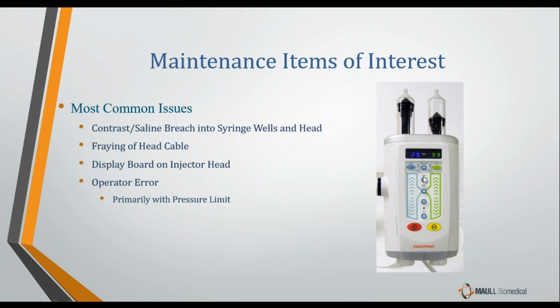So the display board on the injector head, again, it's not every year, but of all the components on an injector, the display board is one of the more highly failure-prone items for the reasons that I mentioned. And then, like a lot of equipment, or most, I'm assuming we're all biomeds here, operator error is one of the other big maintenance issues that you will have with the injector.